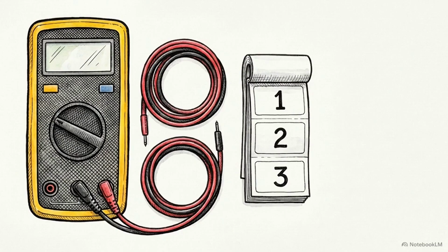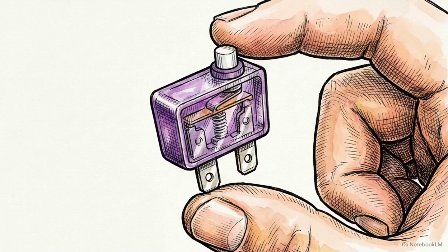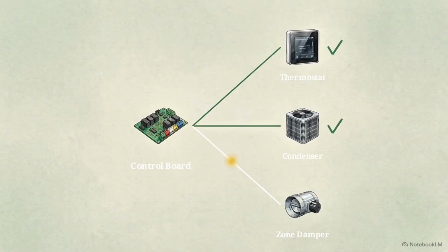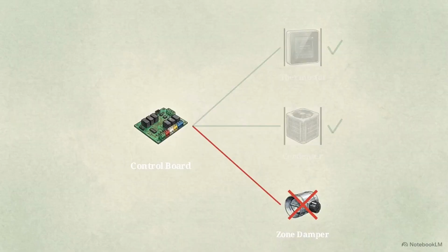To execute this method properly, you will need a digital multimeter, wire labels, and a resettable low-voltage circuit breaker designed for HVAC diagnostics. By applying a rigid process of elimination, you can trace a fault directly to its source without destroying a handful of fuses along the way.